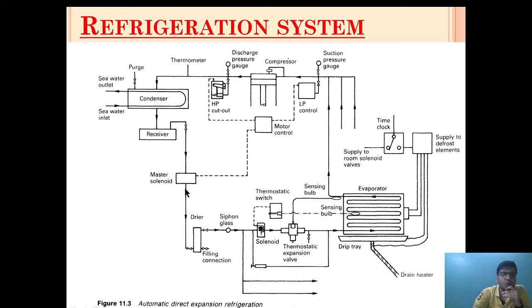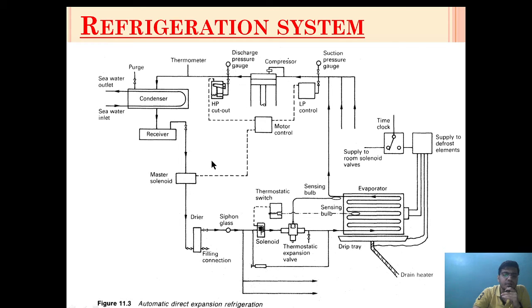A master solenoid is provided which will prevent the flow of refrigerant if any fault occurs in the compressor. The master solenoid valve gets its signal from a motor controller or a device which assesses the condition of the LP and HP. If there is any LP or HP cutout, it will prevent the starting of the master solenoid, and as the master solenoid closes, it will prevent the flow of refrigerant. After the condenser, the refrigerant will flow and pass through a dryer.